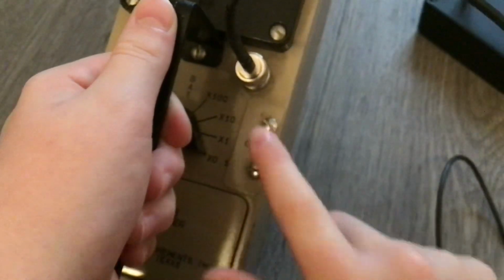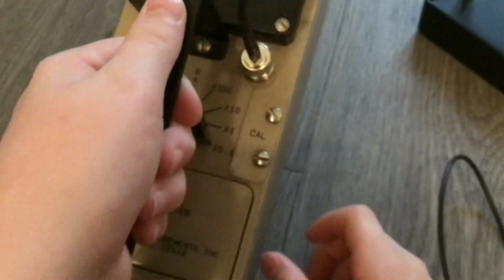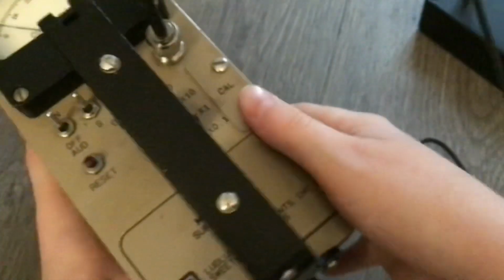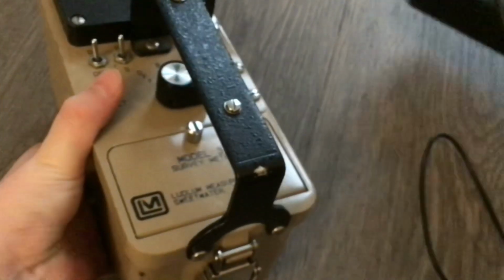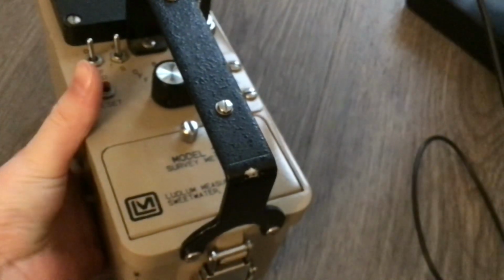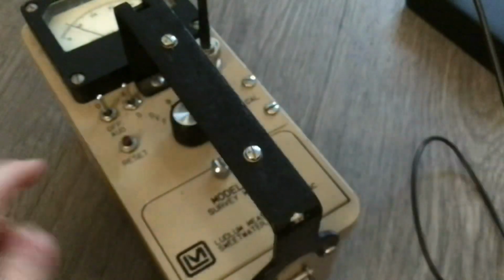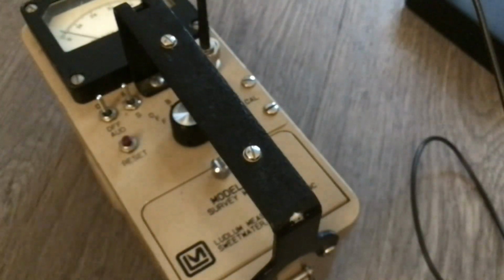This unit can have a scintillator put on it and everything. You might have to unscrew these 2 screws and adjust the high voltage if you want to put a scintillator on here. This probe that I have right now hooked up to it runs at 900 volts. Most GM detectors do. And to reset the meter reading, you can just press that reset button.